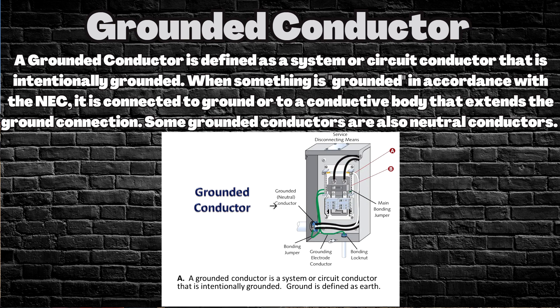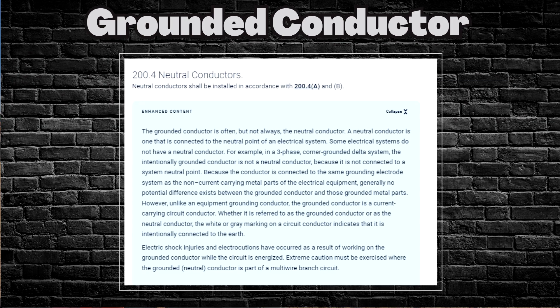Neutral conductors shall be installed in accordance with NEC 2020 section 200.4(a) and (b). The grounded conductor is often, but not always, the neutral conductor. A neutral conductor is one that is connected to the neutral point of an electrical system. Some electrical systems do not have a neutral conductor — for example, in a three-phase corner-grounded delta system, the intentionally grounded conductor is not a neutral conductor because it is not connected to a system neutral point. Generally, no potential difference exists between the grounded conductor and grounded metal parts, but unlike an equipment grounding conductor, the grounded conductor is a current-carrying circuit conductor.